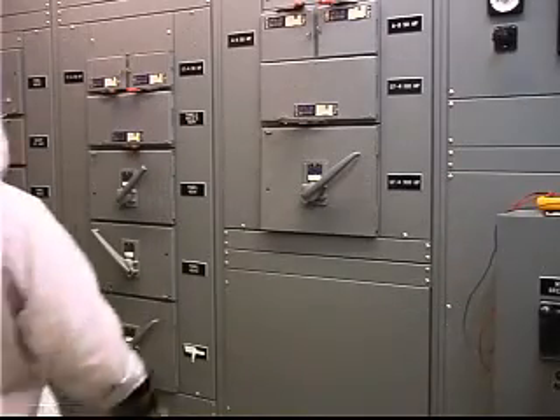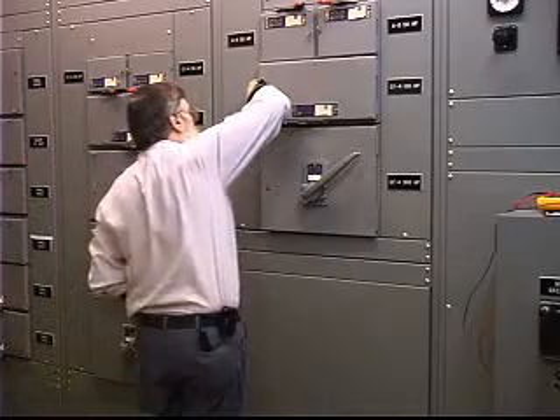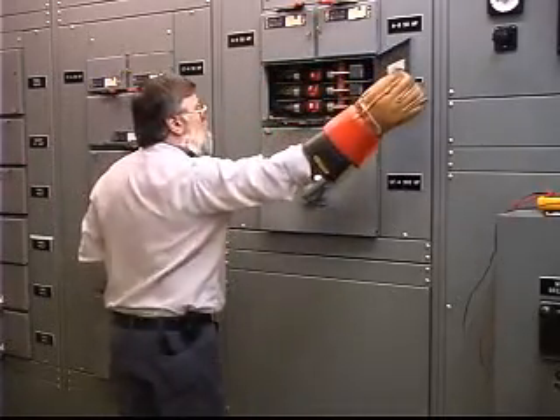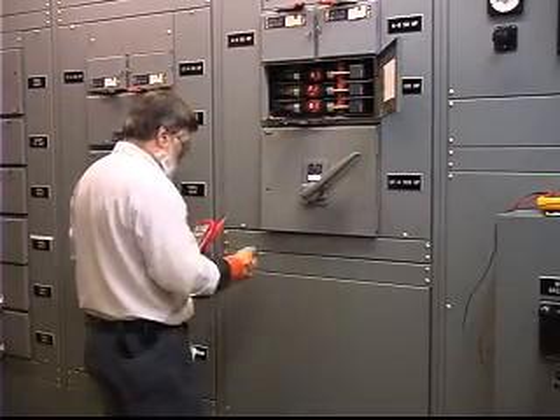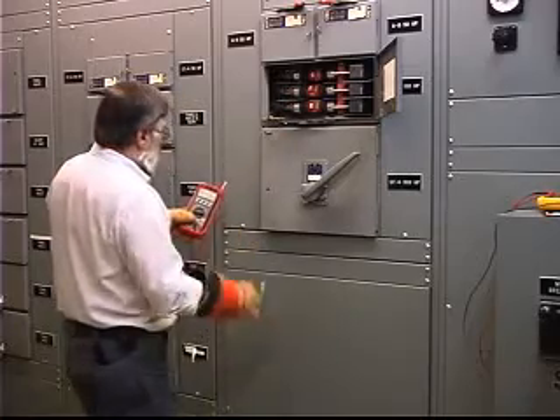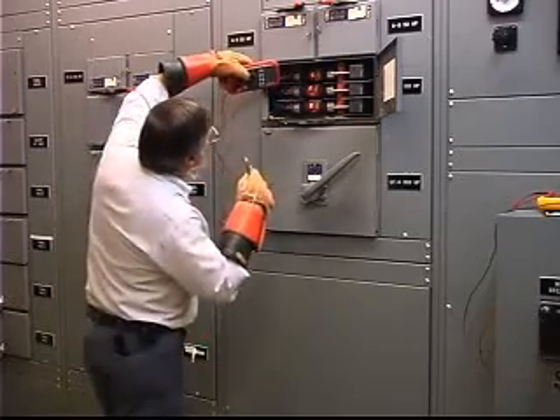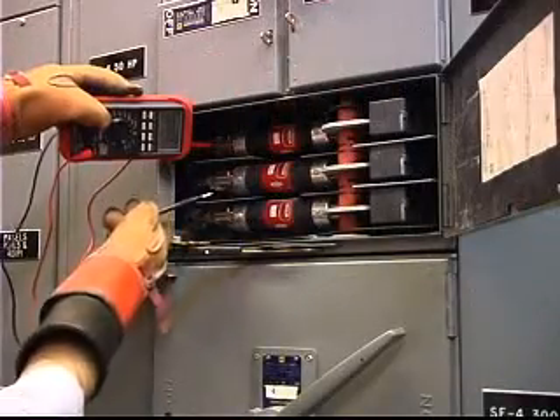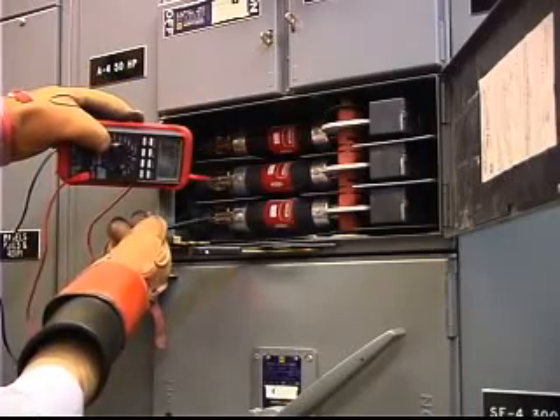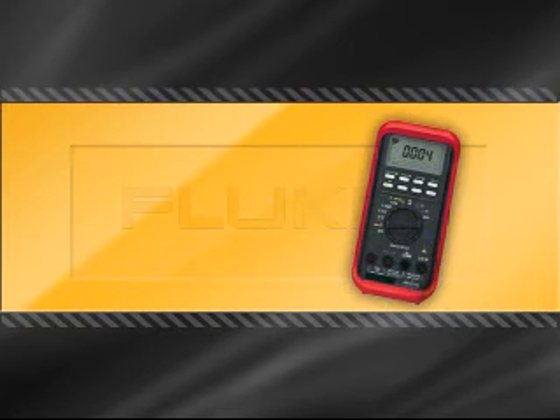Let's take a closer look at why transients are so dangerous. In this example, a service technician is making a phase-to-phase voltage measurement on a 480-volt motor supply circuit. This is a Cat 3 environment. A major voltage transient caused by load switching or a nearby lightning strike was large enough to cause an arc to strike inside the meter.